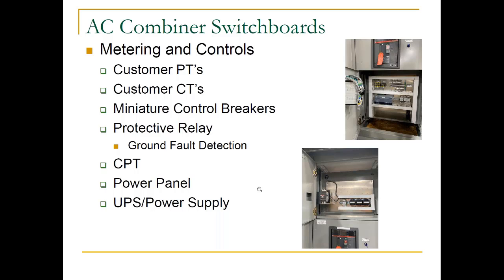We can do different protective relay functions, either off of a breaker that opens, and when that breaker feeding the zigzag transformer opens, it might trip the main breaker, or a zigzag transformer might have a residual ground fault detection type CT connected, and that is what opens the main AC disconnect.